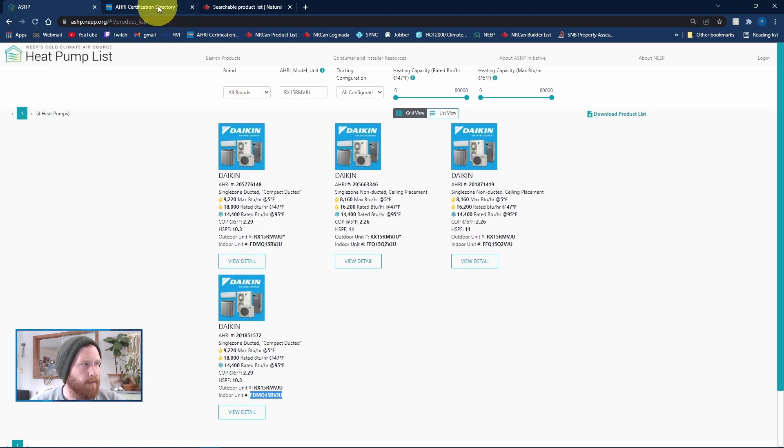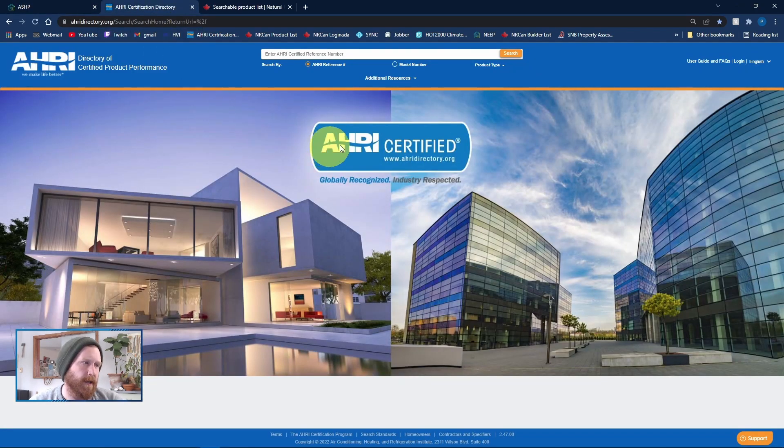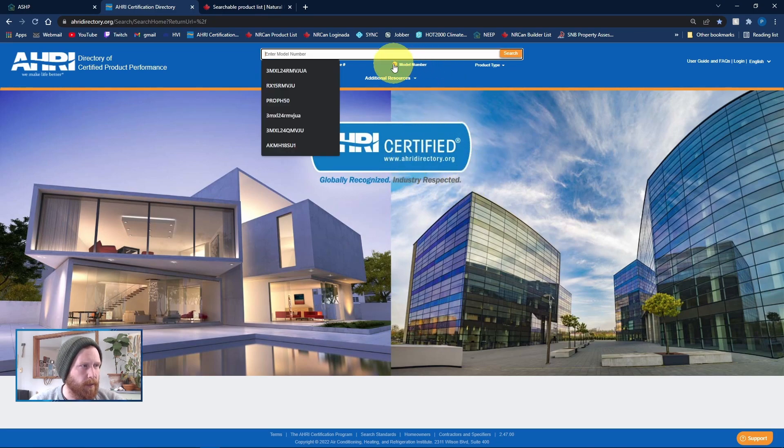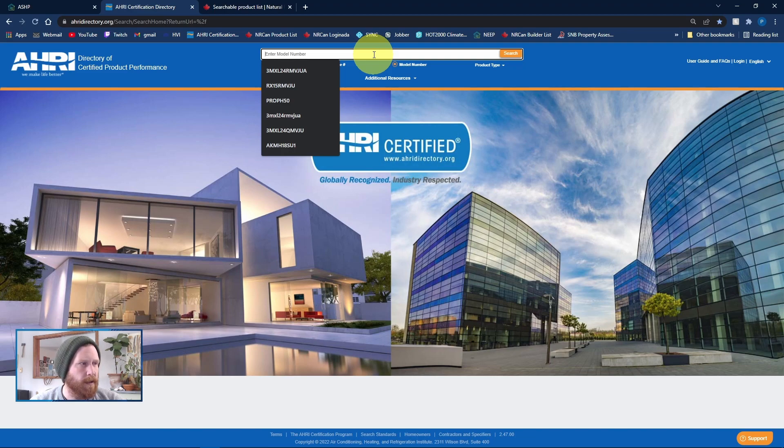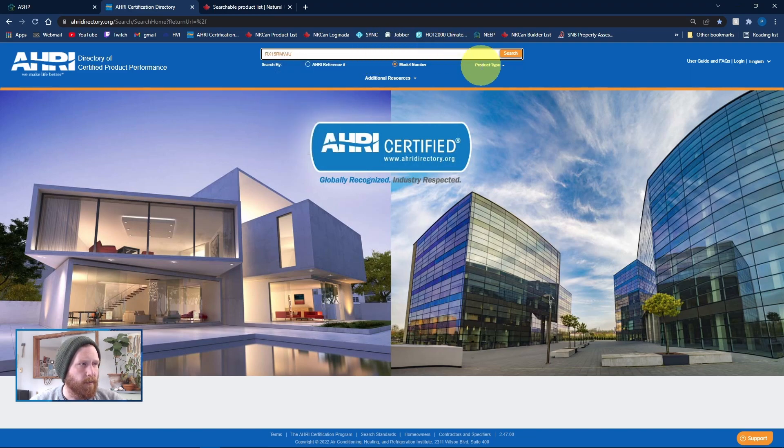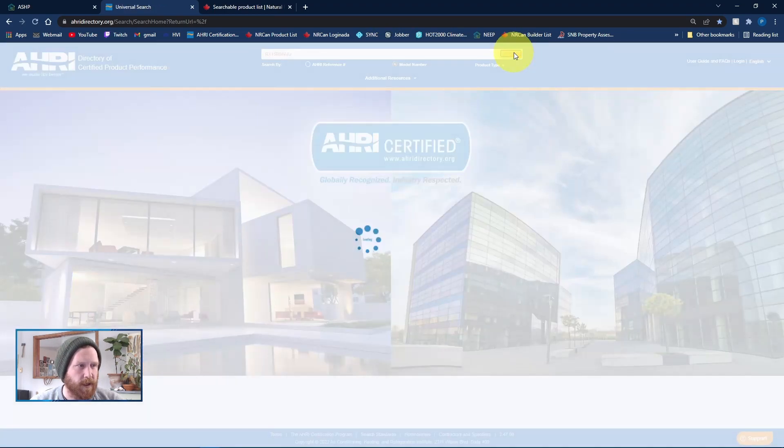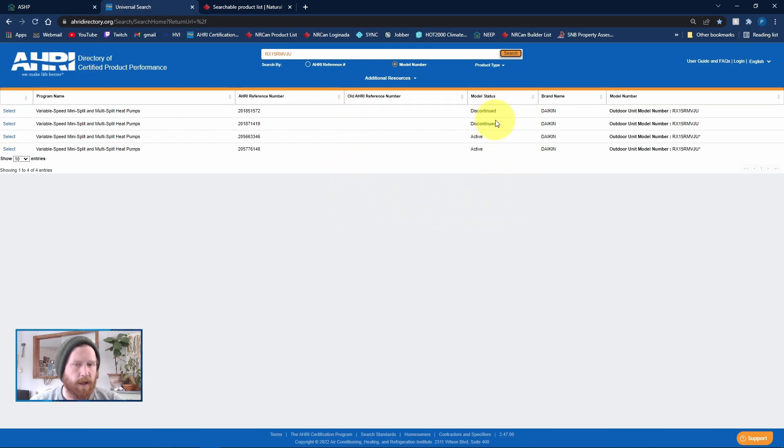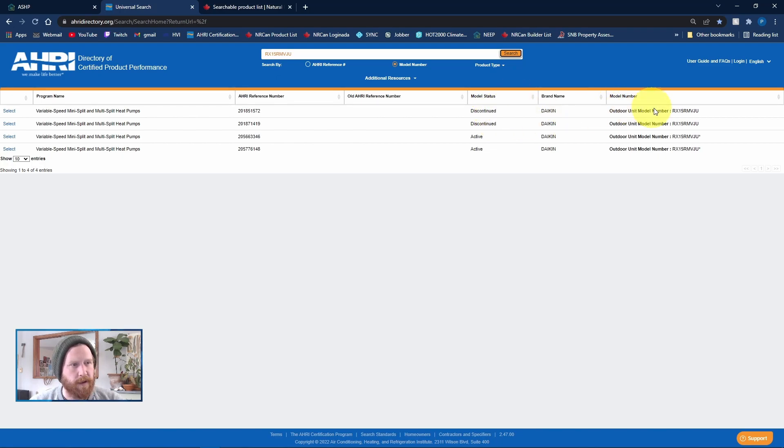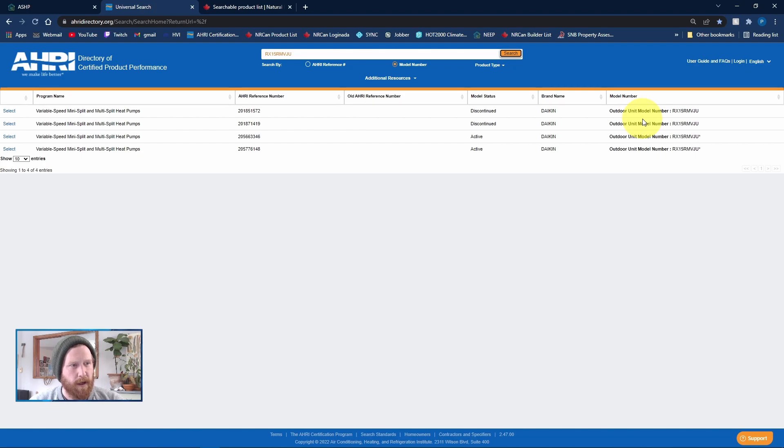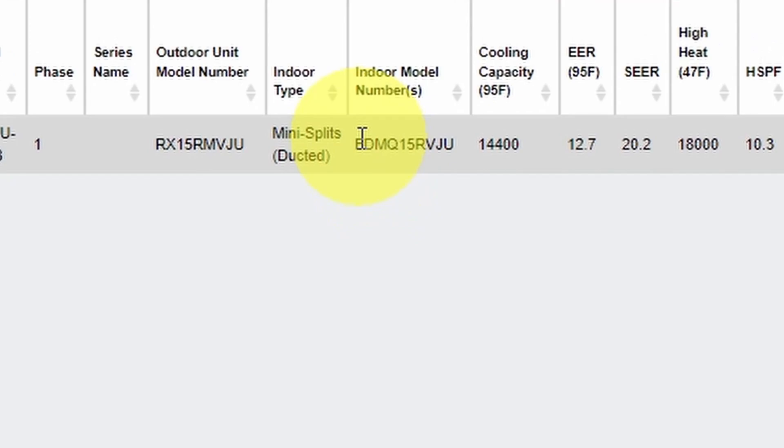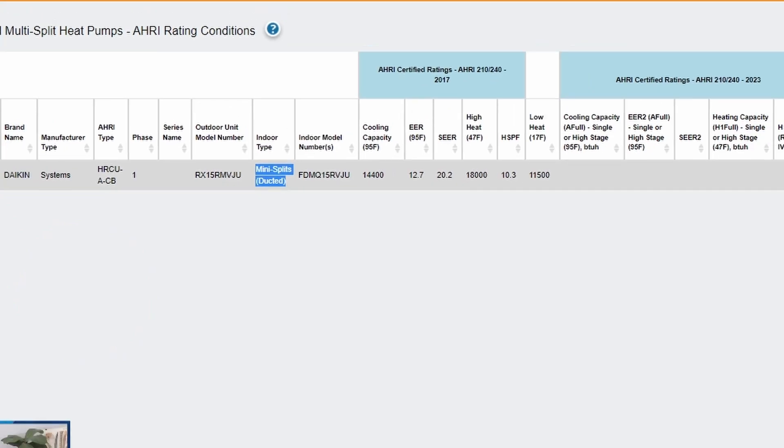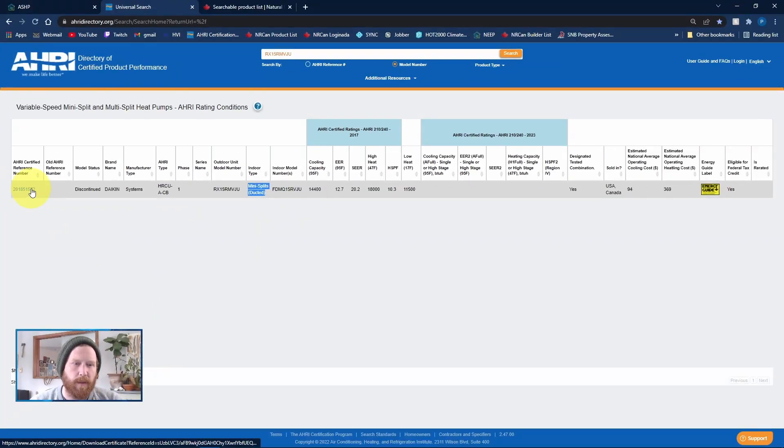Then we would move on to the AHRI directory. So on this website, you just want to search by model number. If you already have the AHRI number, that's great. Just put it in. We're going to search for the same one here. Click search. You can see we get four possibilities and we've got two that are discontinued. These could just be older units if you're doing a D file. But basically you just want to look for the outdoor model number. In this case, we don't have an extra letter at the end, so we're not going to use the asterisks. But what we want to do is just check the first one, hit select, check the indoor model number to see if it's right, and check the type to make sure that makes sense as well. If it does, we would click here and download the PDF and use that to get our specs.